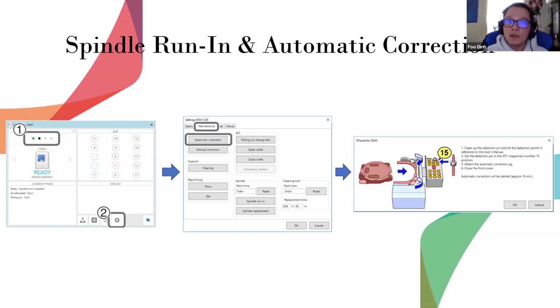Any bit of zirconia dust will cause continuity issues that will keep the mill from making an electrical connection to calibrate the mill. Okay, so what I'm gathering about this process is that you're using that calibration tool that you put in slot number 15, like you said, to make an electrical connection between that and this calibration disc here, and essentially that's what tells the mill exactly where the moving parts of itself are. So it's a really, really important step.